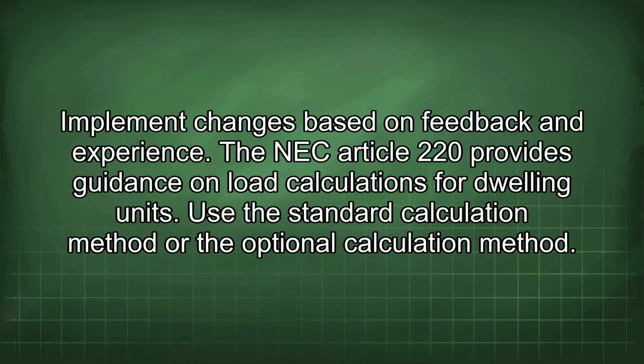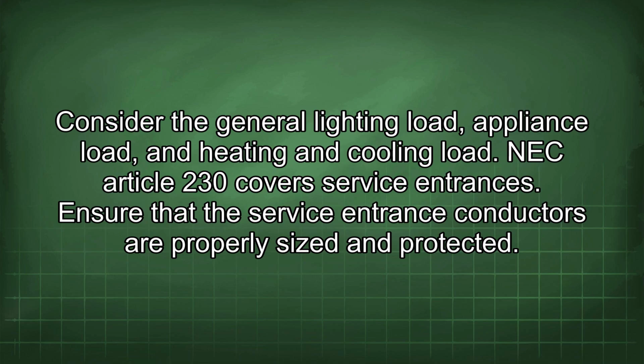NEC Article 220 provides guidance on load calculations for dwelling units. Use the standard calculation method or the optional calculation method. Consider the general lighting load, appliance load, and heating and cooling load.